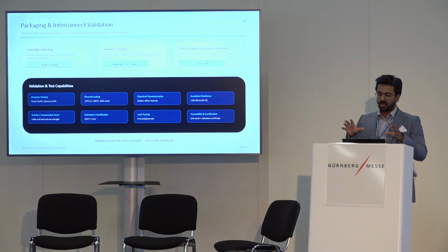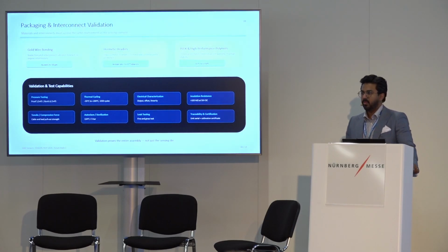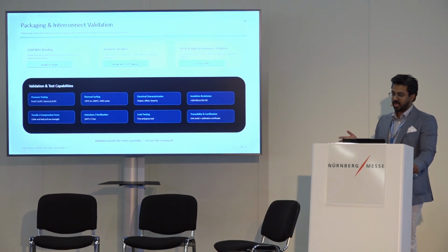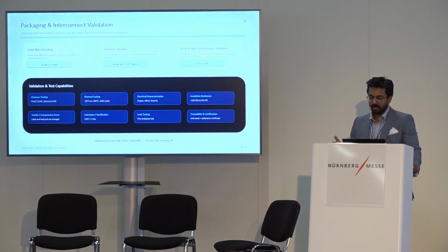Three key technologies at the top: one thing we work with heavily is the sensing element and the pads that connect it to the rest of the electronics. We do gold wire bonding, which gives a clean, fine-pitch interconnect with no organic intermediary. We use hermetic headers for cavity protection, and PEEK and similar high-performance polymers on top, which give chemical and sterilization compatibility for medical, aerospace, or defense-grade applications.